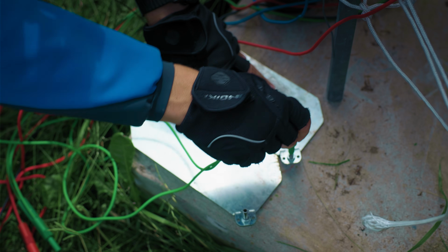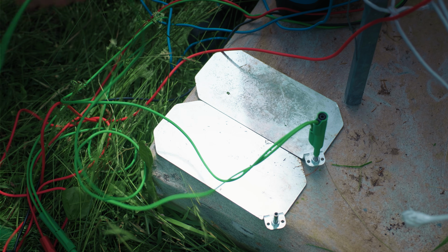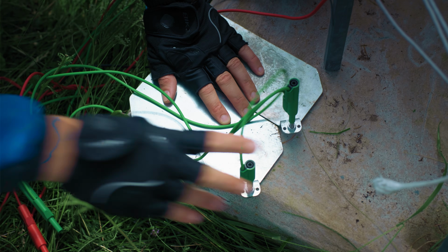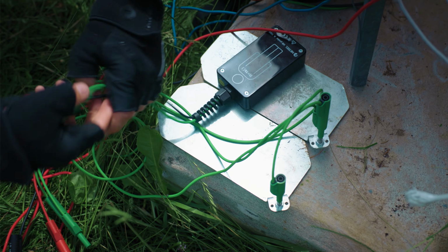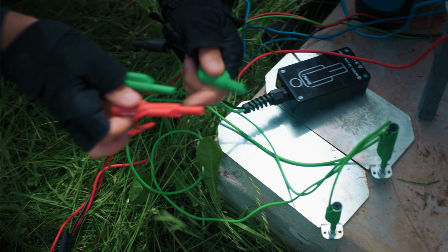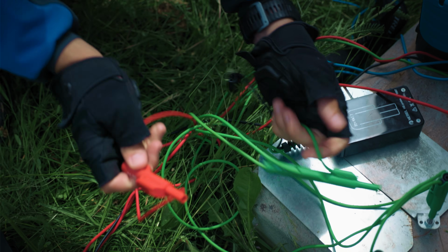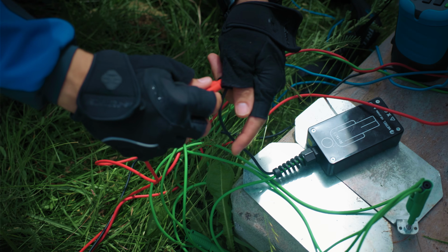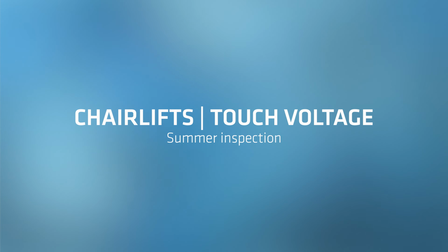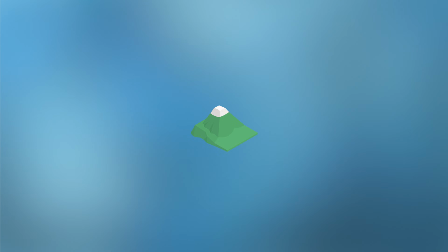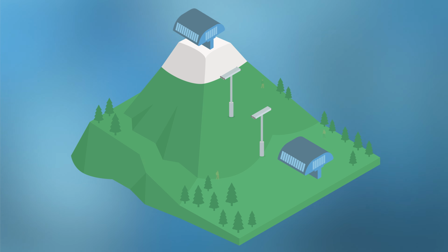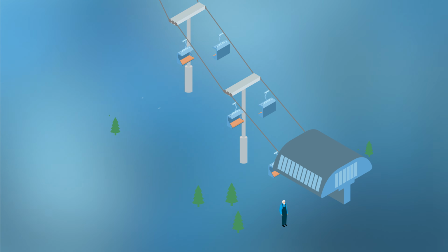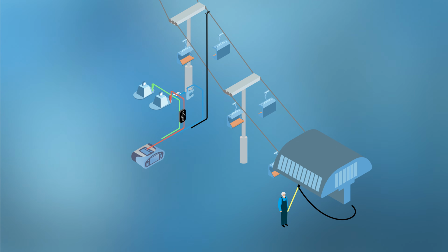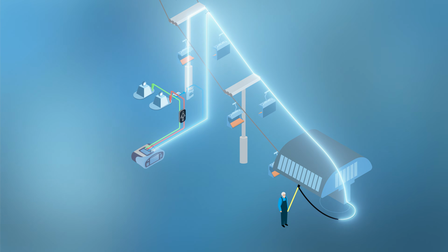For accurate evaluation of touch voltage, two test plates are connected to simulate bare feet on ground contacts, while the A1597 human body resistance probe represents the resistance of the human body. Tests should be executed at different positions around conductive parts at a distance of 1 meter.